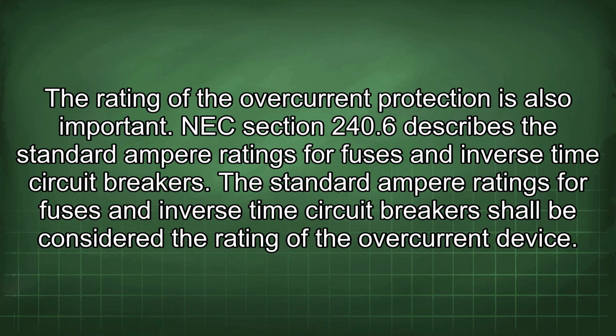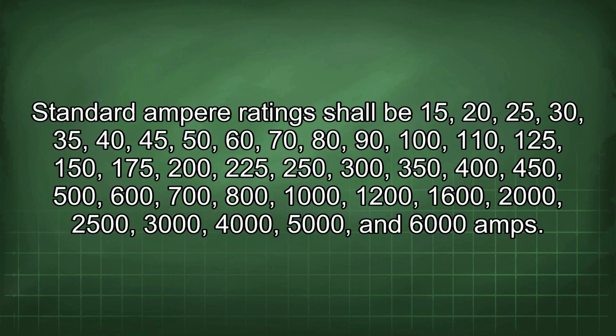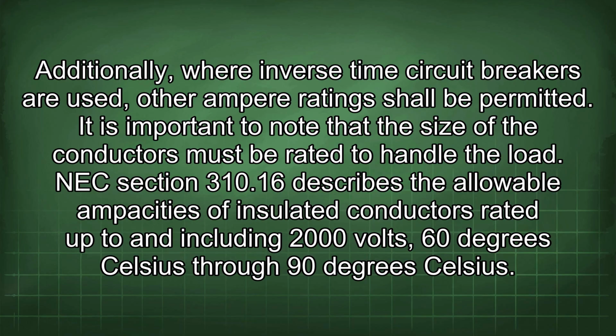The rating of the overcurrent protection is also important. NEC Section 240.6 describes the standard ampere ratings for fuses and inverse time circuit breakers. The standard ampere ratings for fuses and inverse time circuit breakers shall be considered the rating of the overcurrent device. Standard ampere ratings shall be 15, 20, 25, 30, 35, 40, 45, 50, 60, 70, 80, 90, 100, 110, 125, 150, 175, 200, 225, 250, 300, 350, 400, 450, 500, 600, 700, 800, 1000, 1200, 1600, 2000, 2500, 3000, 4000, 5000, and 6000 amps. Additionally, where inverse time circuit breakers are used, other ampere ratings shall be permitted.